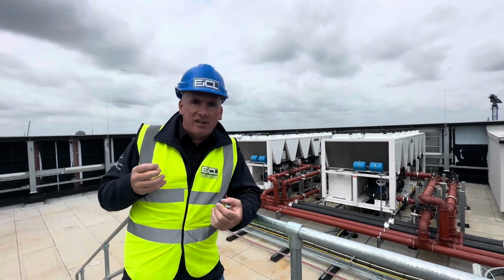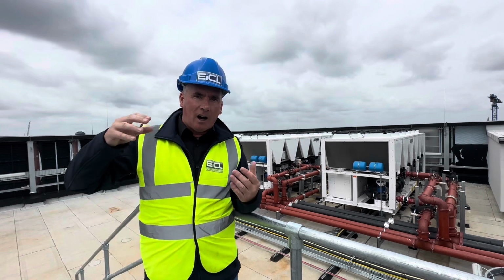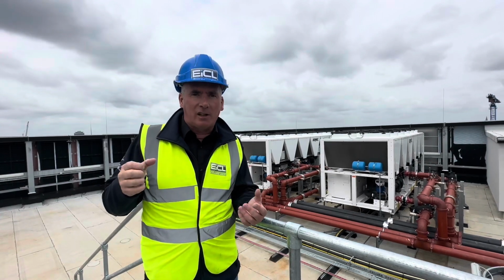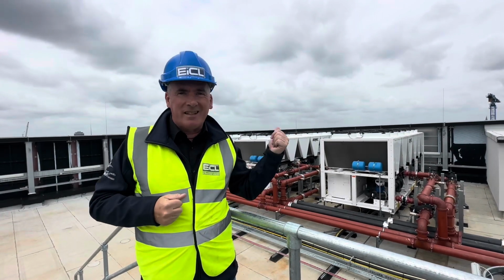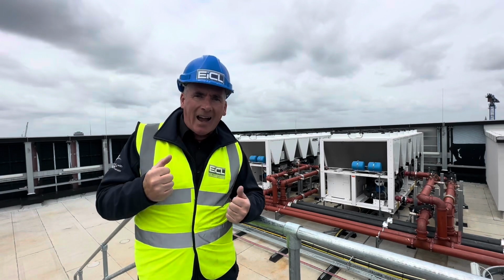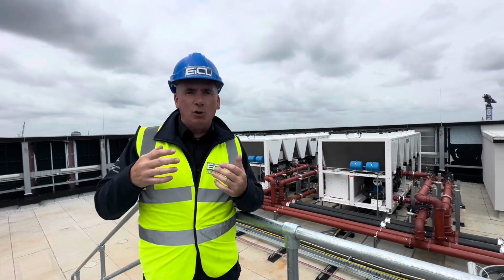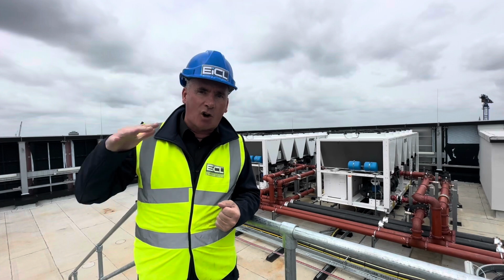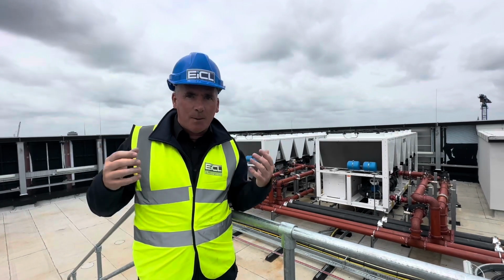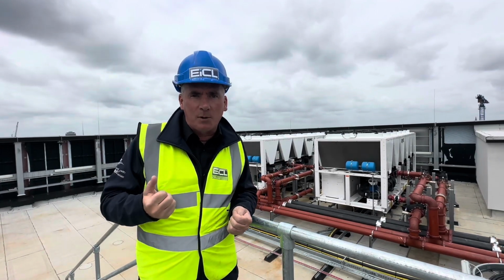But we design our system as efficiently as possible, where we have our LTHW, typically 45-40, like I said, and the chilled water, typically 6 and 12, 7 and 12. By the way, you can have a dynamic set point. You don't necessarily need to have the same temperature all year round. Obviously, as the ambient temperature changes, a lot of people are used to weather compensation you would have had on boilers.